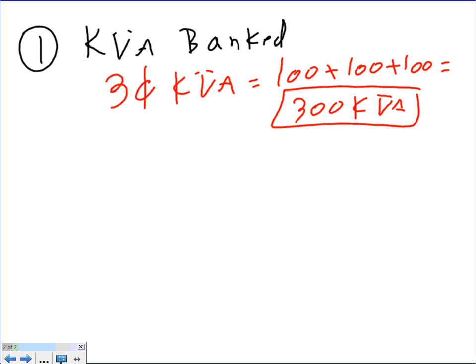Excuse me, sir, why do you have then 150 here in the middle? Because to give a three-phase, each transformer has to give the same amount of kVA. But in the middle we have 150. Now, transformer number 1 and 3 can give only 100 kVA, so the one in the middle cannot give more than 100. So what you're asking me, what happened to the other 50?